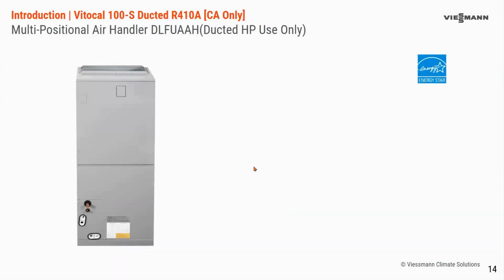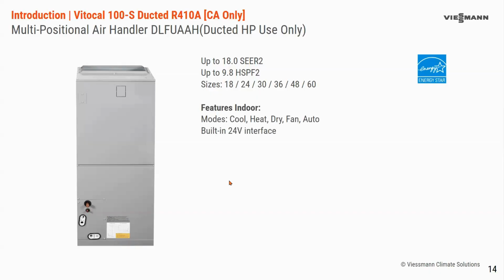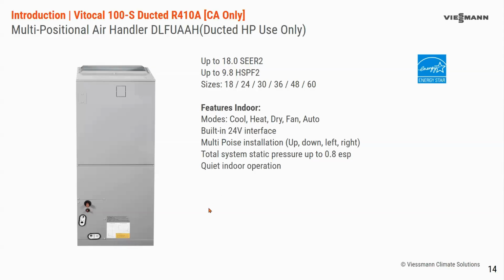So for the four-way multi-position air handler, this is essentially the same air handler that was seen on the ductless, but this has the line sets for the ducted, and it does have an EEV, whereas the ductless air handler does not have a metering device at the indoor, since that's controlled by the EEVs outside.